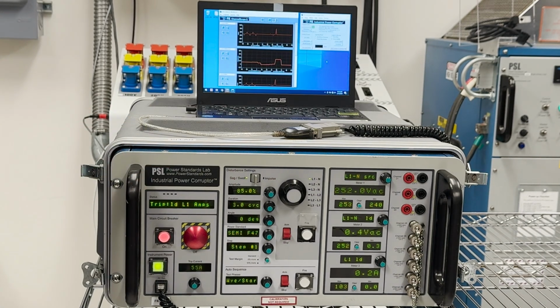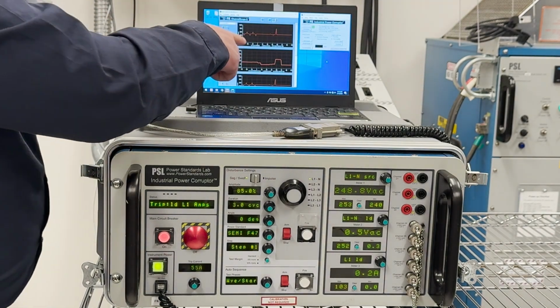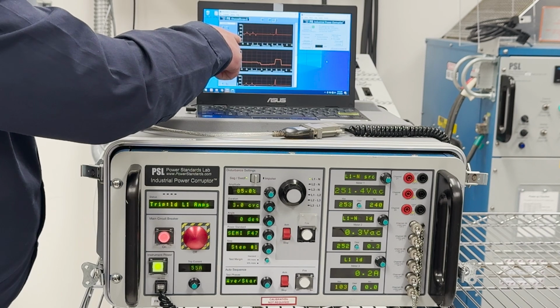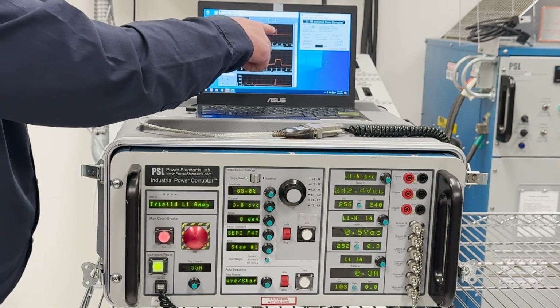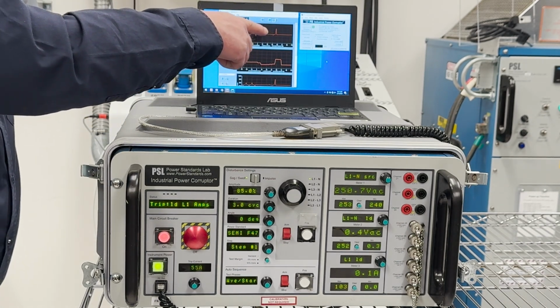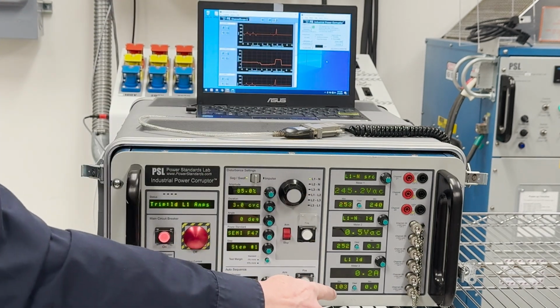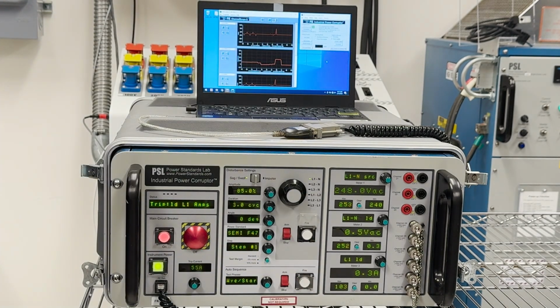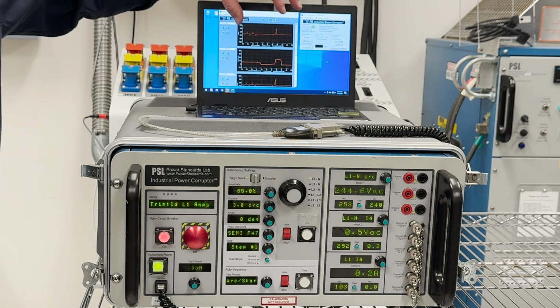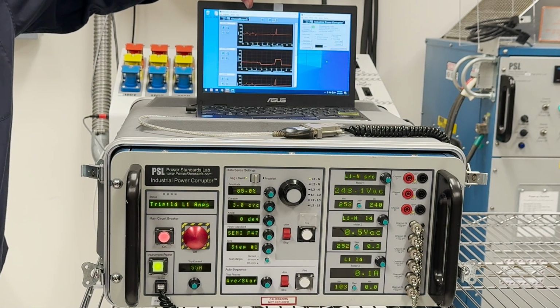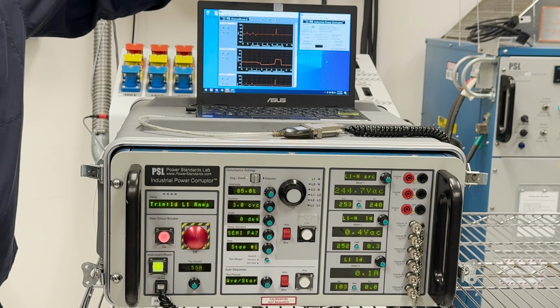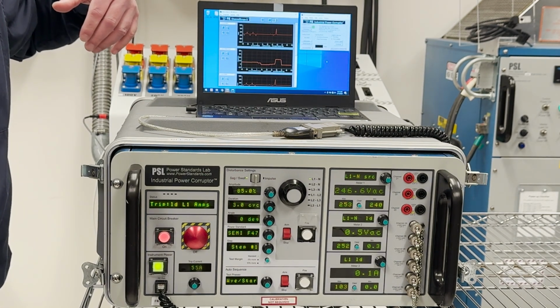Yeah, one more thing, if you look at the graph here on channel scope, you can see that the amps here exceeded 600 amps. That is significant, right? So although the peak is showing about 100 amps on the meter here, channel scope has picked up the characteristics of this. So make sure when you download that you properly validate that you're staying within reasonable limits of the IPC. We don't want you to damage it. Moreover, we don't want to damage your equipment under test.